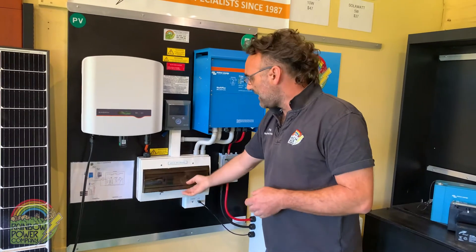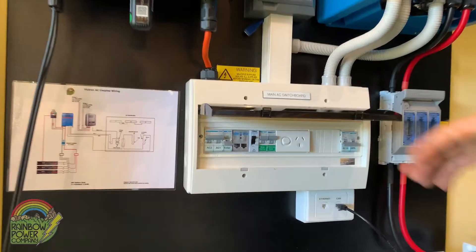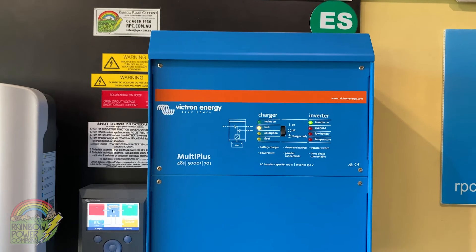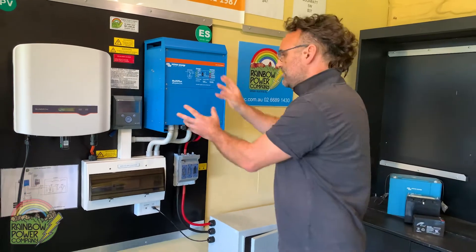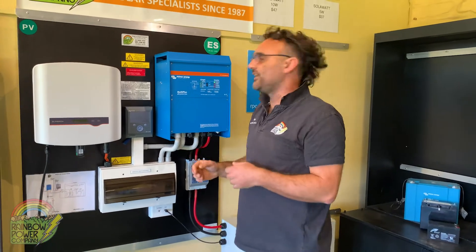We've got our distribution board, our main AC distribution board, with all the fusing and switching required so that you can actually get power out of the system. We've also got our multi-plus inverter charger. This is actually the heart of the system and it's what converts the 240 volt and solar power into 48 volt battery power. So it's actually charging the batteries during the day and then taking the power from the batteries at night to supply your loads.